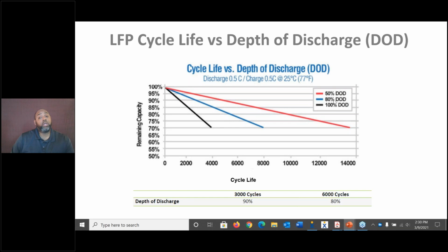If you look at this chart, the red line represents 50% depth of discharge, and the blue line is 80% depth of discharge. Our batteries are warranted for 10 years at 80% depth of discharge. And if you look at this LFP cycle life versus depth of discharge chart, you'll notice at 6,000 cycles that this battery will last.